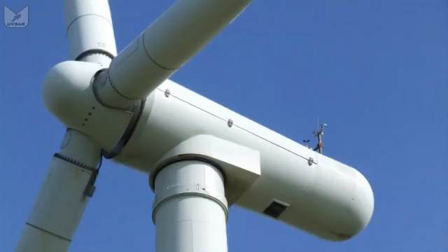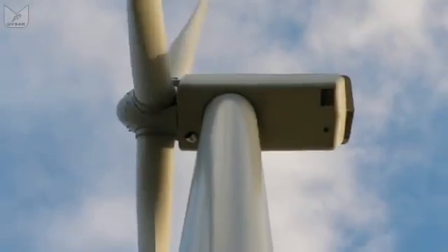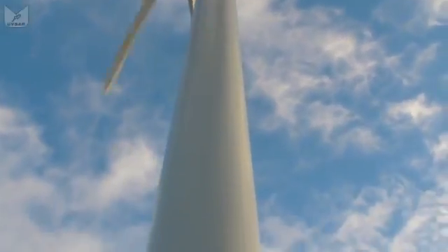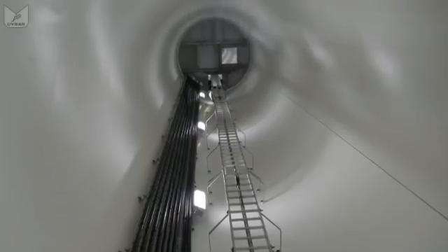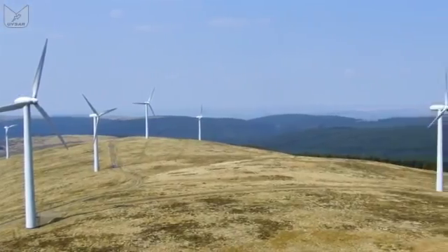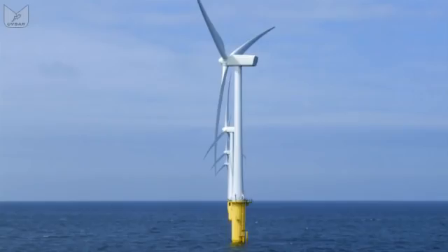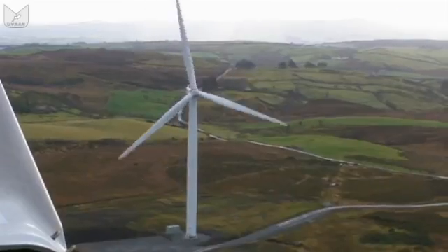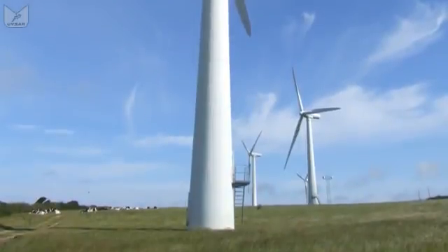And in this nacelle we have the generator, often a gearbox, and occasionally a high voltage transformer, and the whole thing sits on top of a tower, which is mostly there to keep the blades from digging a hole. We tend to class turbines by their power output, and hence their physical size. Wind farms might use many sub-megawatt turbines, each producing 400, 600 kilowatts each, or a few multi-megawatt turbines, producing maybe up to 3 megawatts per unit. Apart from physical scale, they are arranged a bit differently, so let's start by looking at a typical sub-megawatt model.